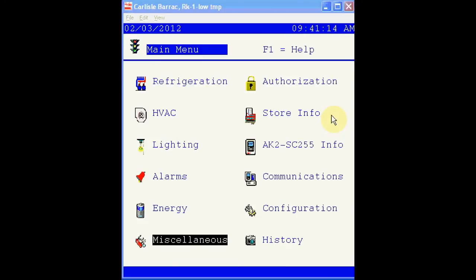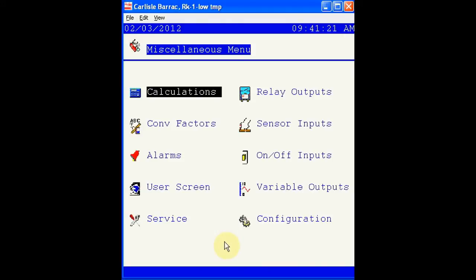Let's take an overview of the miscellaneous screen, which contains many useful functions. Calculations are used to make decisions or copy sensors. Conversion factors can be used to build sensor types not already included in the AK2-SC255. Alarms gives you a link to setting miscellaneous alarms. The user screen can be used to display a list of important inputs or outputs on one screen. The service menu allows you to offset miscellaneous sensors and override miscellaneous relay outputs or on-off inputs.